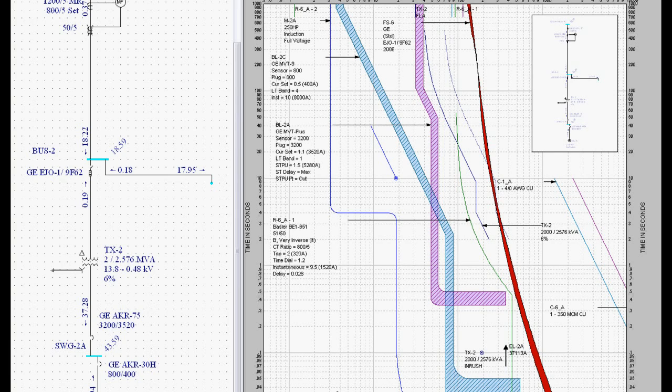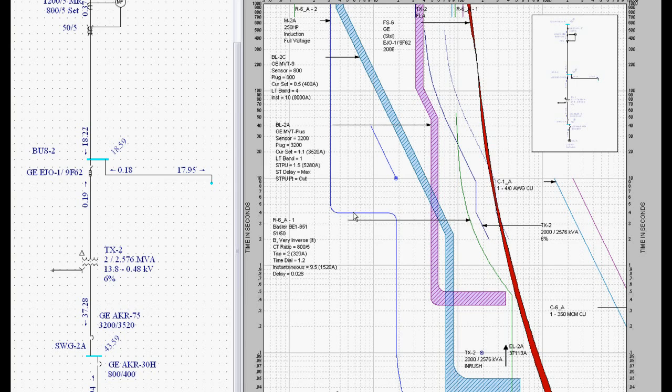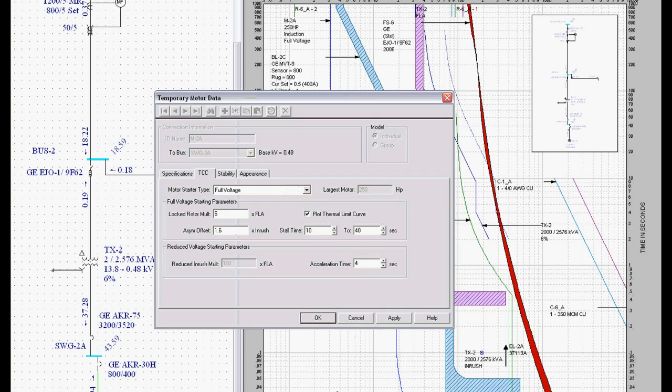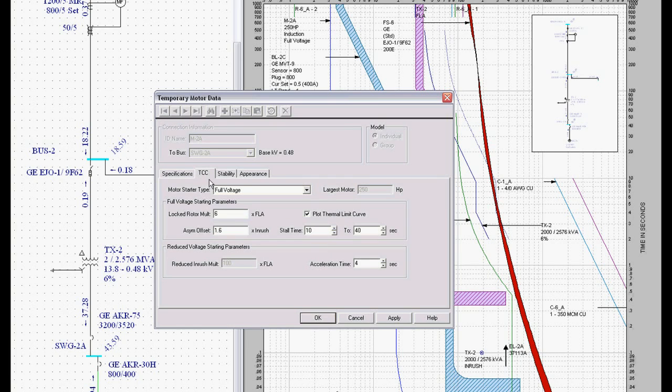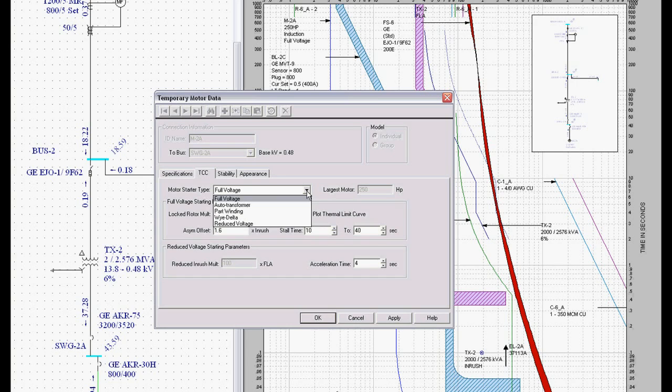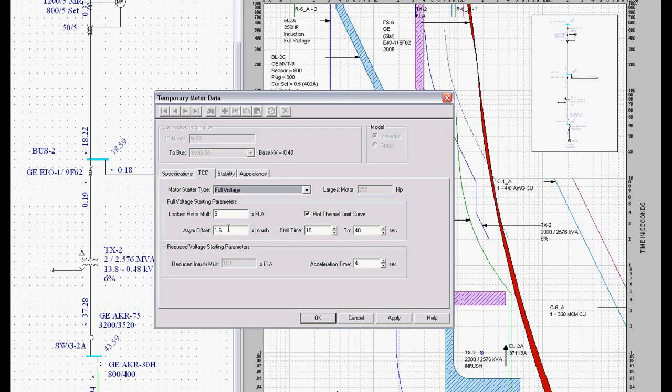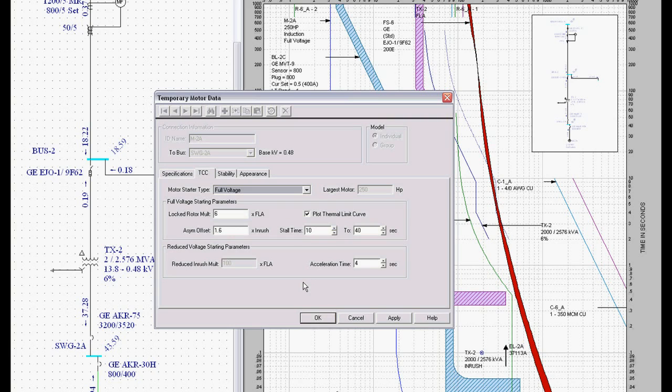Here is the motor starting curve for this motor. And I could come over here and click on this motor and here's my TCC tab describing that information. So we can determine whether this is a full voltage, an auto transformer, a part winding, Y delta, reduced voltage starter, any way we want. We can modify all our locked rotor multipliers and asymmetrical offsets and things.